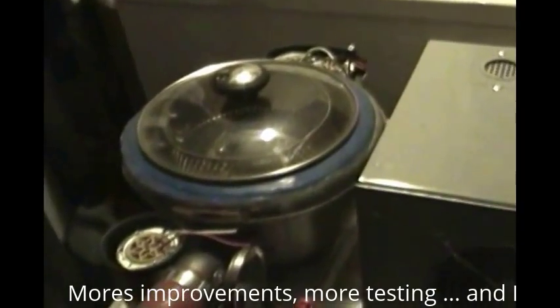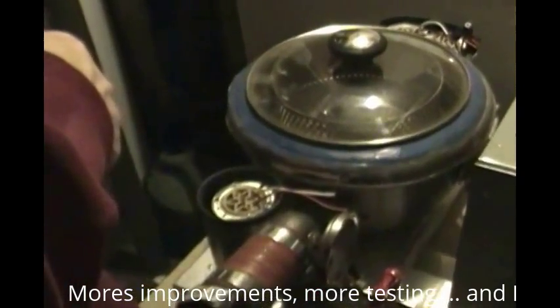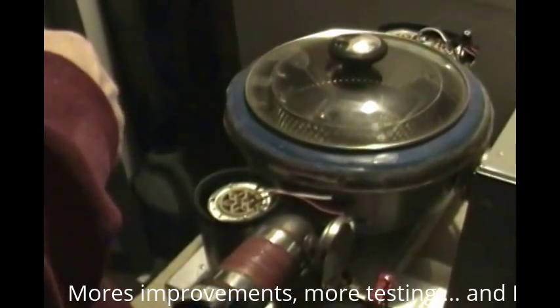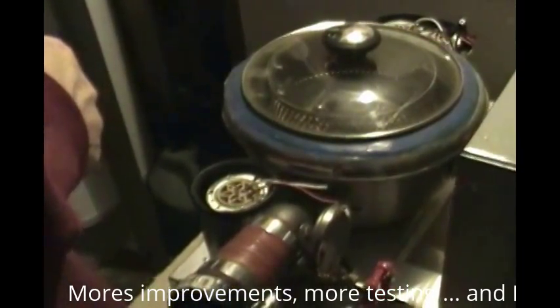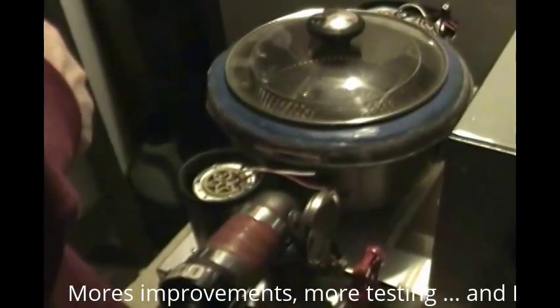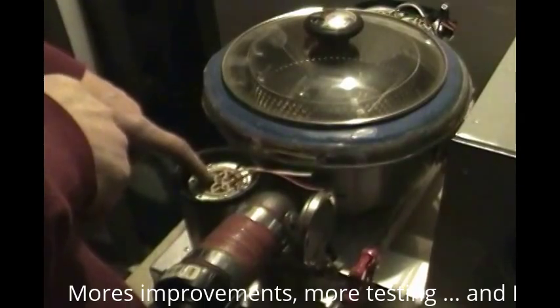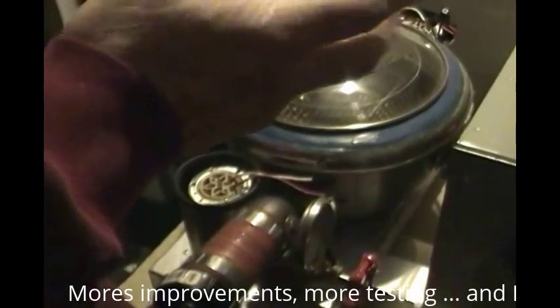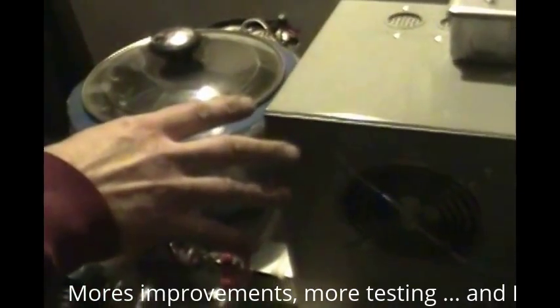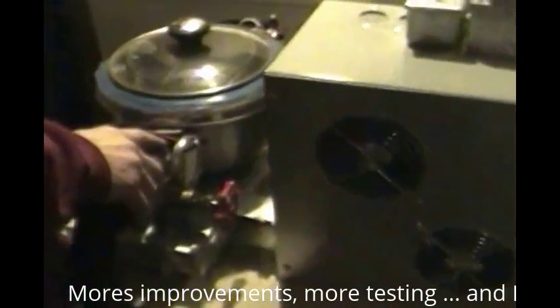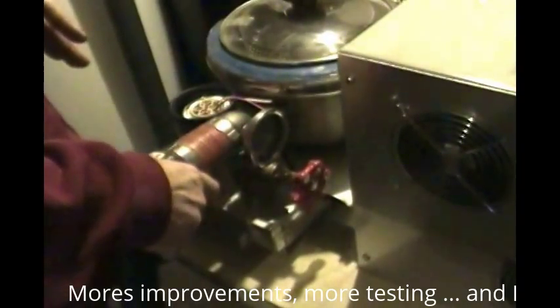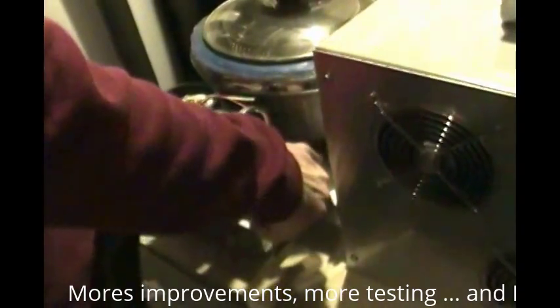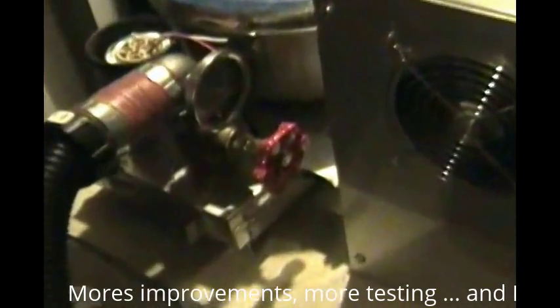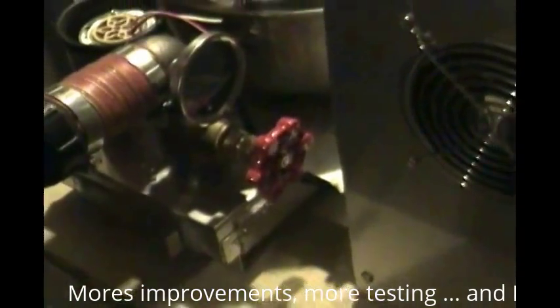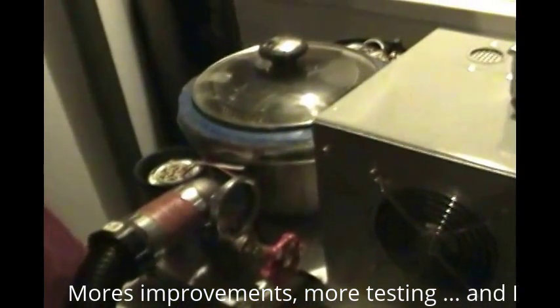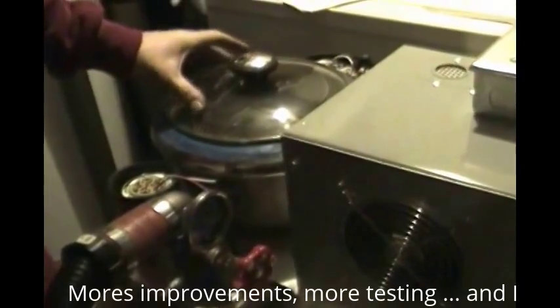Now, we've had some issues with the heating elements burning out, and I believe it was caused by a heat exchange unit that we had previously, which was cutting down on the volume of air actually going through the heating elements, causing them to superheat and burn out. So we took out the heat exchanger port and substituted it with this special cooling down system, which is turned off now. I'm hoping that combined with a couple of adjustments I made in the PID is going to stop the heating elements from getting fried.